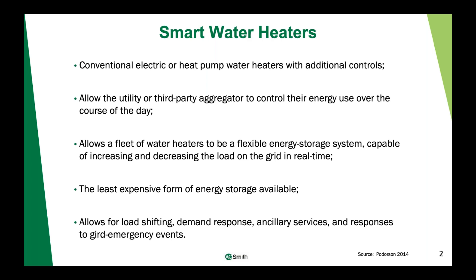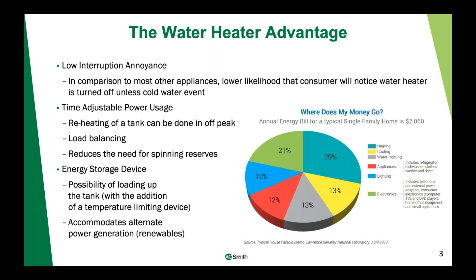Smart water heaters are essentially conventional electric or heat pump water heaters with additional sophisticated controls. They can allow a utility or third party aggregator to control energy use during the course of the day. Within a given local territory, a fleet of water heaters can be controlled altogether to be a flexible energy storage system that can adjust the load on the grid. Everyone has a water heater in their house, and it has been said this is the least expensive form of energy storage that is available. Smart water heaters must have a balanced load — you must preheat or shift usage in order to have load to recover from.